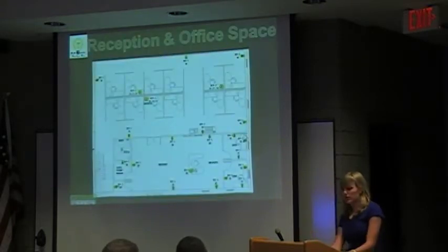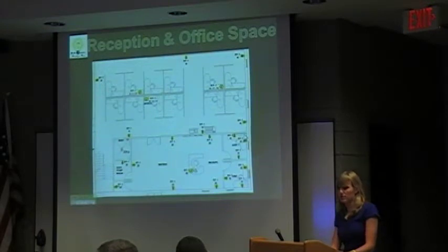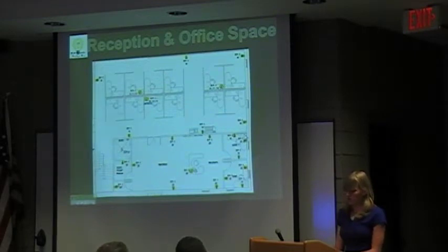In the reception and office space, we place floor boxes underneath all the cubicles to be hardwired to. Then we also place receptacles along the perimeter of the room and try to circuit about 6 to 8 receptacles per 20 amp circuit.